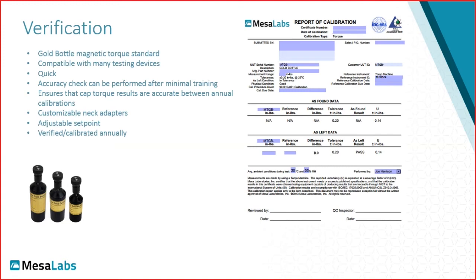So the benefit of this is that it's quick, it's compatible with many testing devices, not just our devices, but manual, automated, and other brand devices. And the accuracy check can be performed with minimal training. The neck adapters can be customized. The set point can be adjusted to different torque levels, and that torque level is determined during a calibration in the factory. But if you send the gold bottle back for recalibration, we can reset it to a different value. The gold bottle should be verified and calibrated annually.